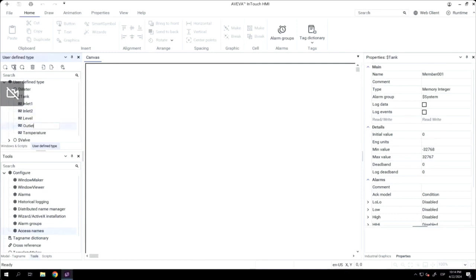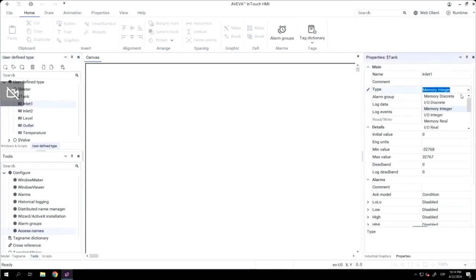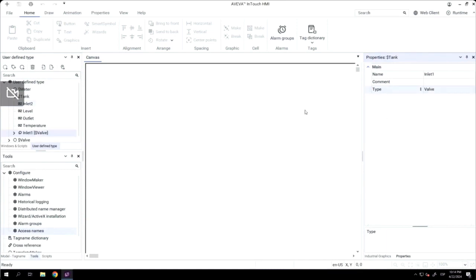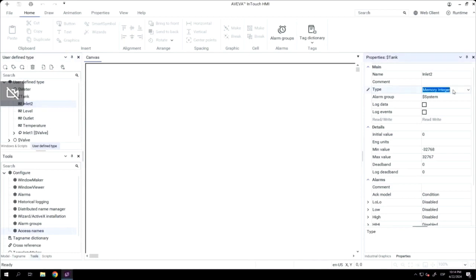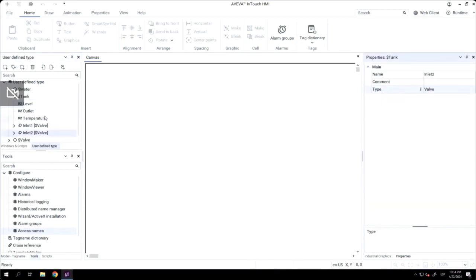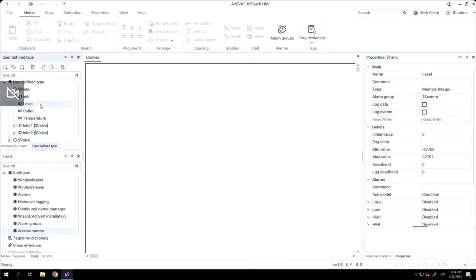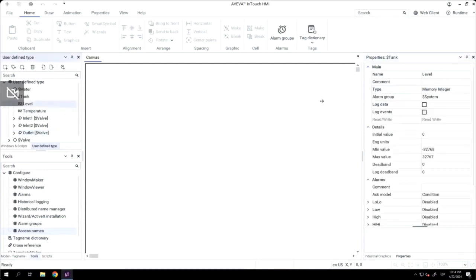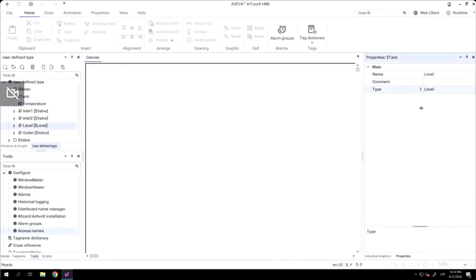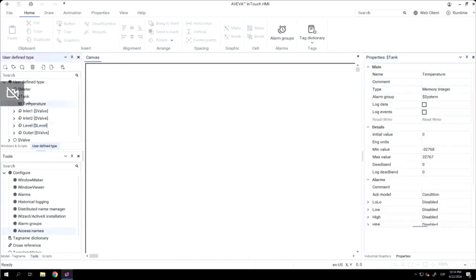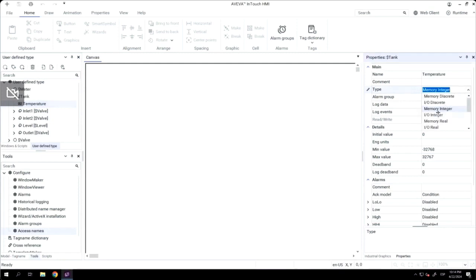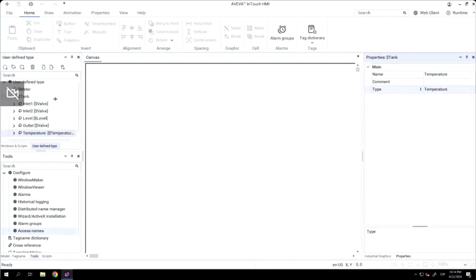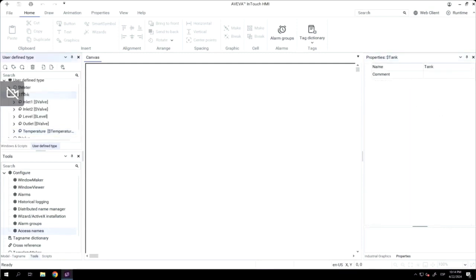The good thing here is we will change the type, and in that case, we will use the previous UDT types that we created previously. For inlet one, inlet two, and outlet, we will use the valve, and for temperature, we will use the temperature user-defined type, and the same for the level. With that kind of structure, we can create complex structures in a very easy way, just quite similar to what we can do in System Platform.